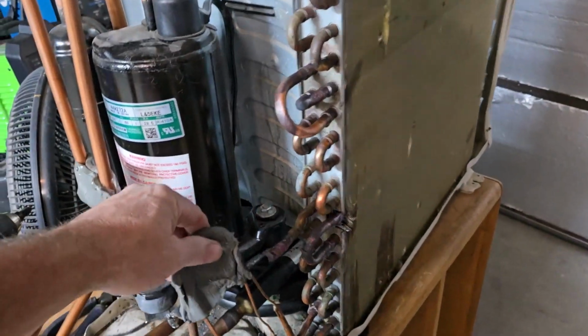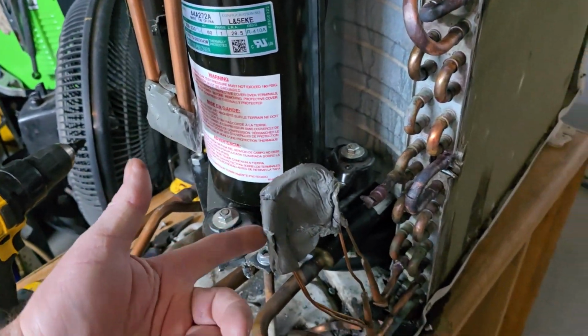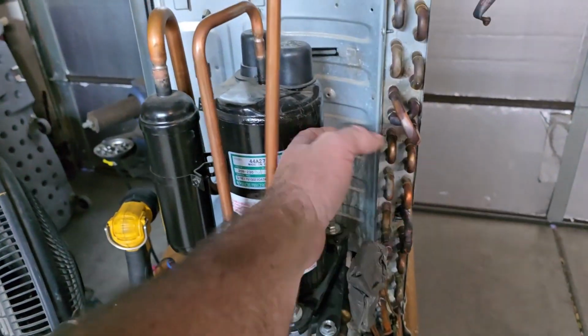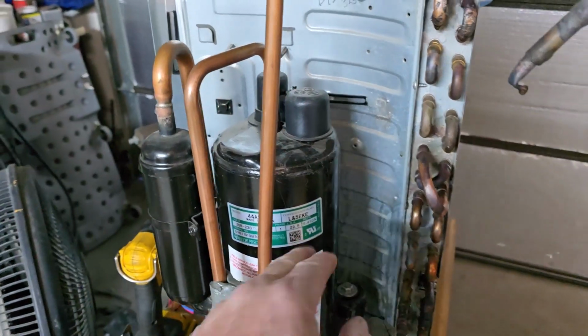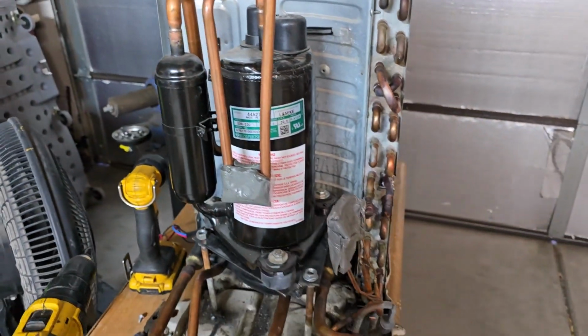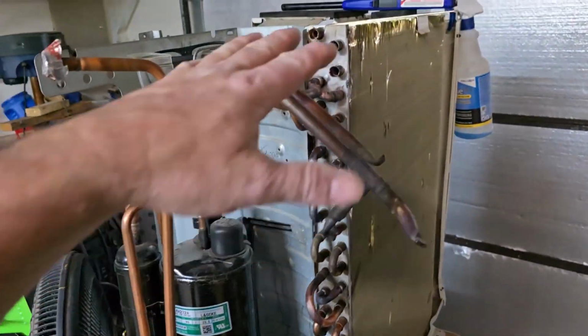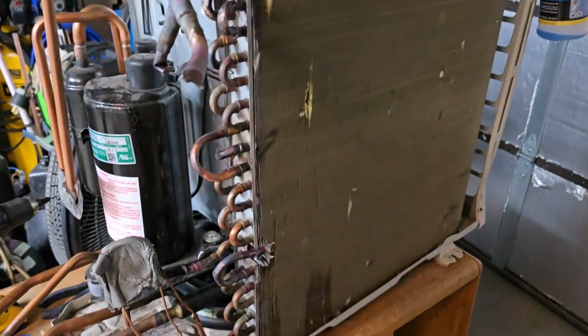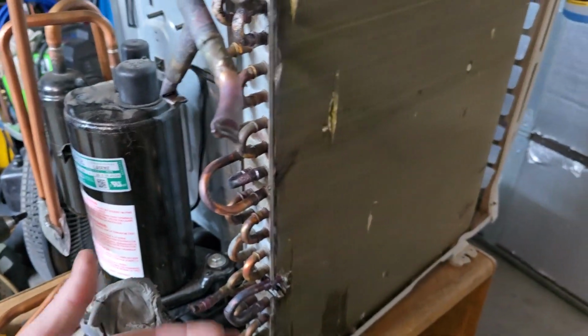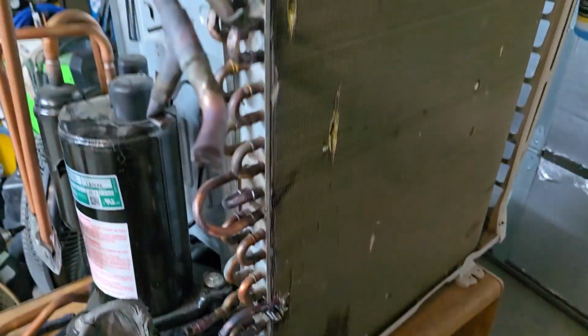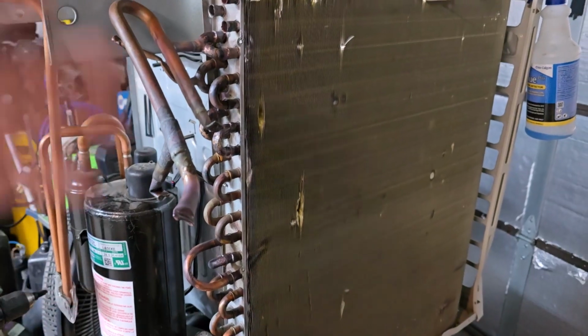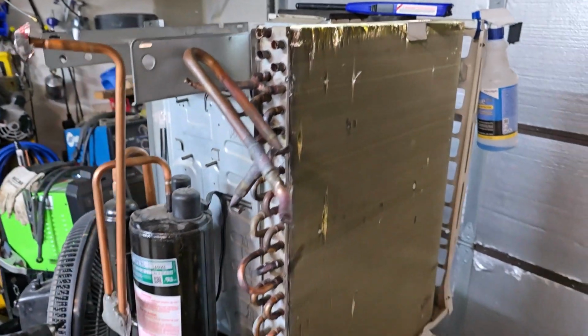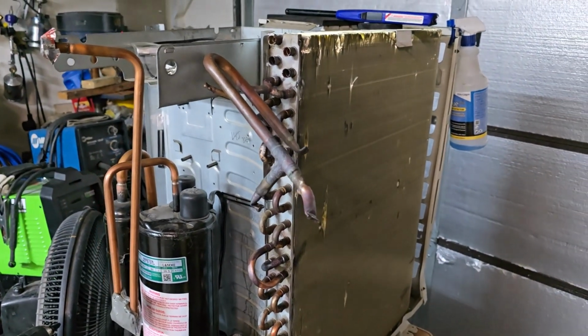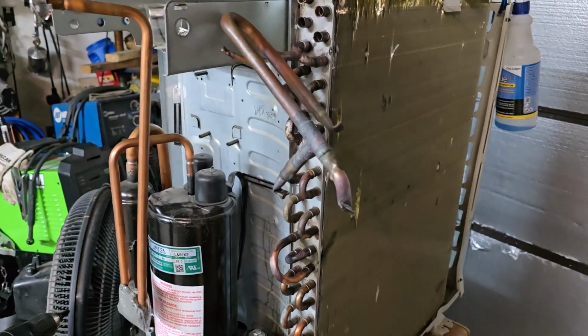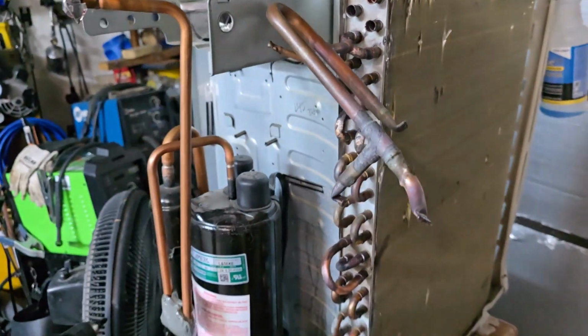So this will be the evaporator. I just used the capillary tube that was already on the system I took this compressor out of - a 10,000 BTU compressor, so it should be about right. This was an 18,000 BTU coil, so I'm not using the bottom subcooler circuit - that's effectively for a condenser. I'm not using the top 2 rows either, so I'm actually using a little more tubing and surface area than I need. I'm just using it to absorb heat for the heat pump, so it should be all good to go.